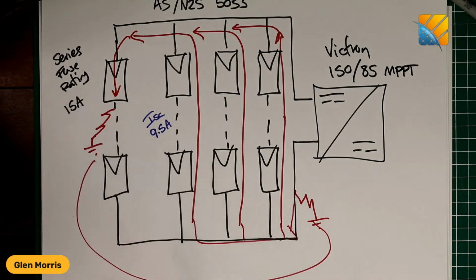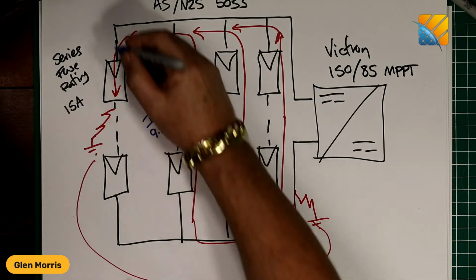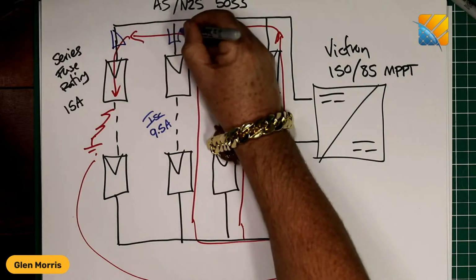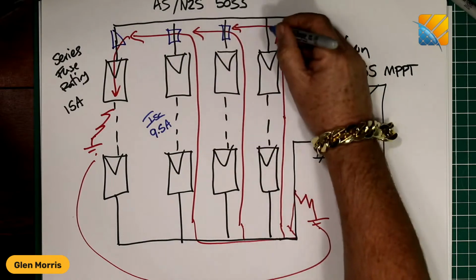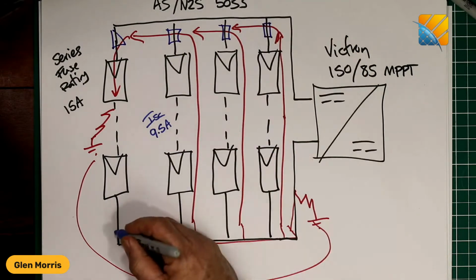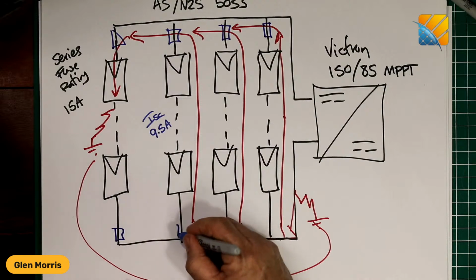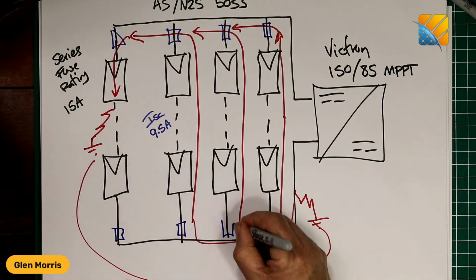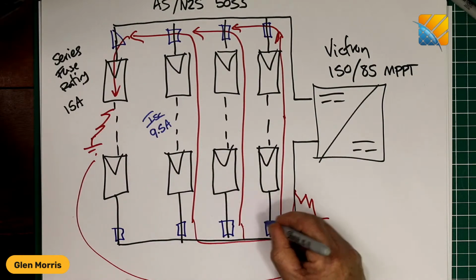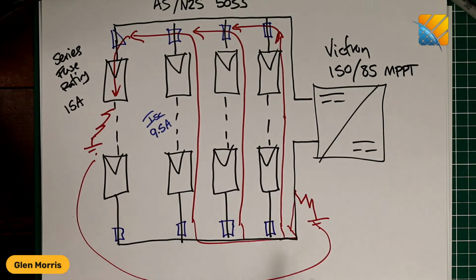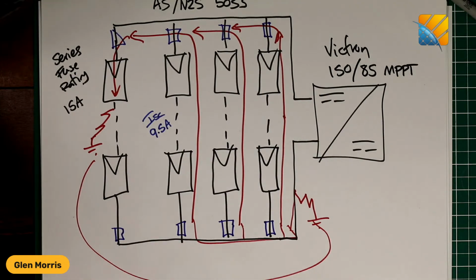You may find panels with a higher fuse rating. By the way, you put the protection as close as practicable to the point of combining the strings, so basically at the ends of the strings, and you have to have string overcurrent protection. They can be fuses or circuit breakers, appropriately designed ones, for both the positive and negative pole of the strings. So there you go. Thanks for that question, Craig. That was a great one.